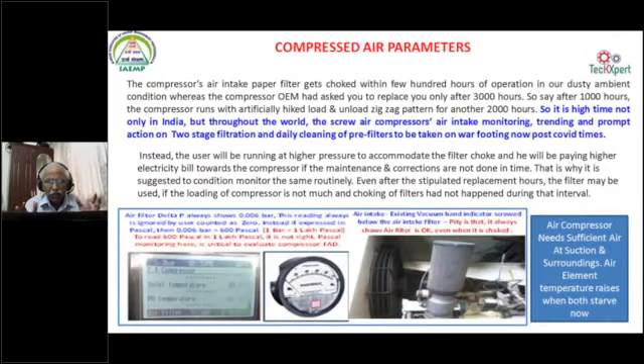Compressed air parameters. See, again, this is a point which I was thinking is happening in our industry. But when they tried throughout India, in all the industries, imported compressors, Indian compressors, everywhere, the free air delivery, or the air delivered freely at the mouth of the compressor, is measured, but not monitored. I don't say the CFM has to be monitored, but at least the differential pressure in Pascal across the air intake filter needs to be monitored.